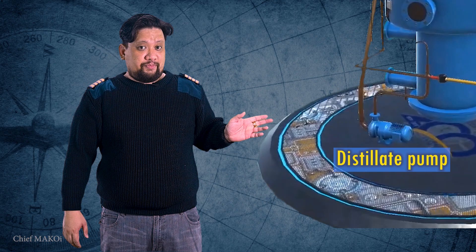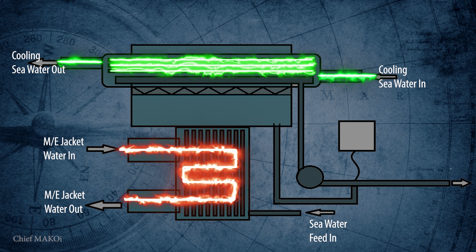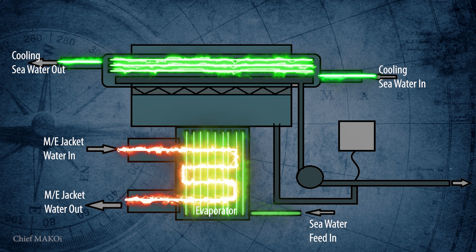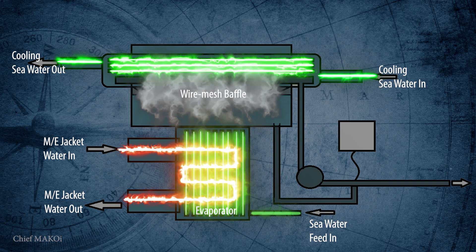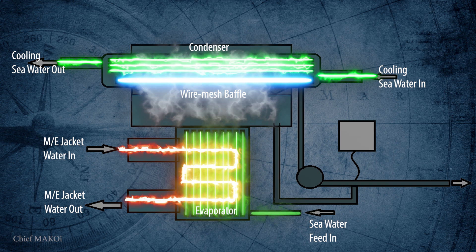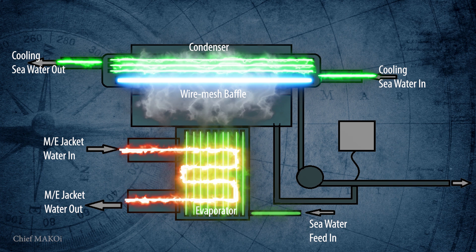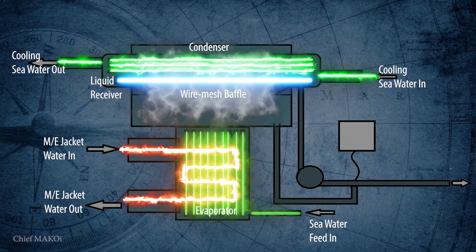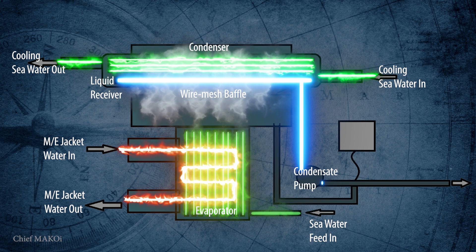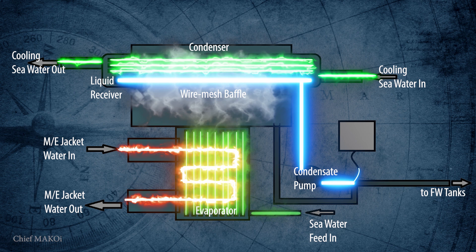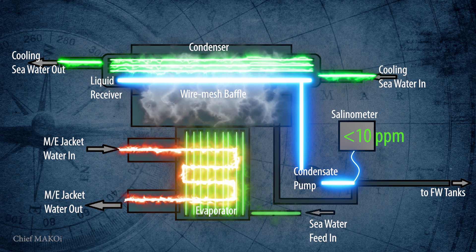So how does the distillation plant work? The flow operation begins when seawater enters the evaporator. From there, it absorbs heat and evaporates, passes through a baffle screen to filter out remaining impurities, and then comes into contact with the condenser tubes where it is cooled down and condenses back into liquid, but this time without the salt content. This condensate is collected in the liquid receiver directly below the condenser tubes, where it is then suctioned by the condensate pump and delivered into the freshwater tanks. Before it can go there, it is sampled and analyzed by the salinometer. If the remaining salt content is below 10 parts per million, the freshwater is delivered into the tanks. If it's higher than 10 ppm, it is diverted back to the evaporator.